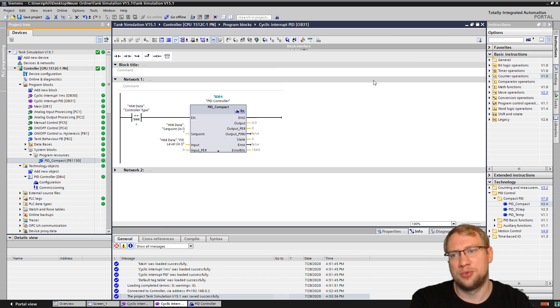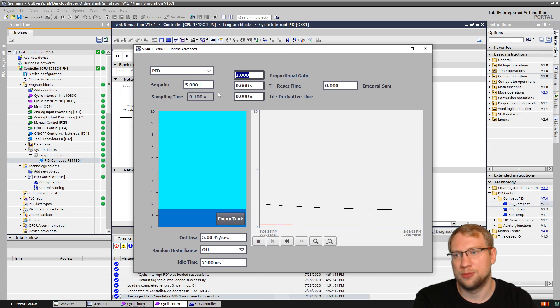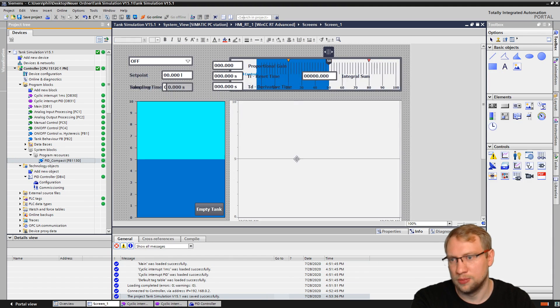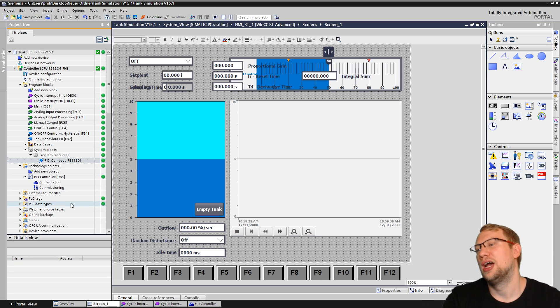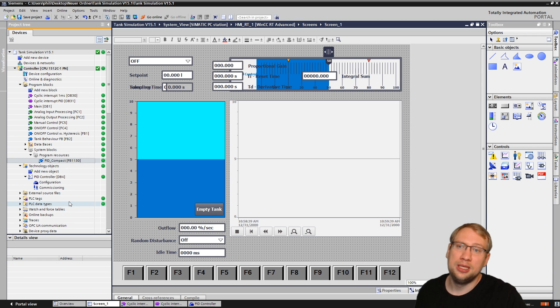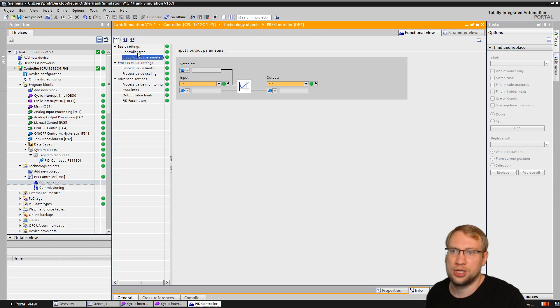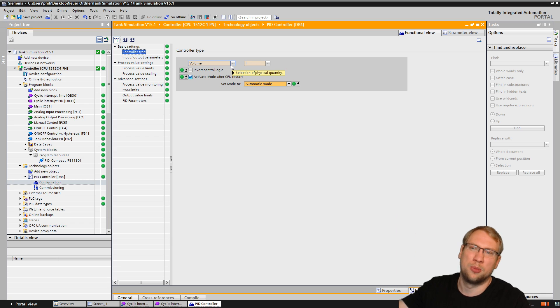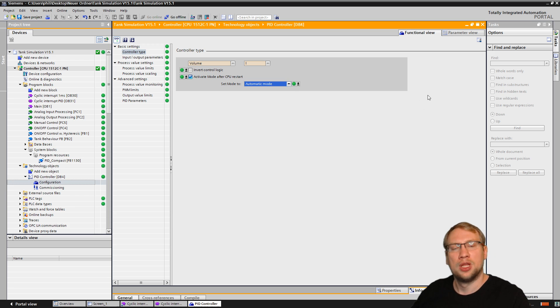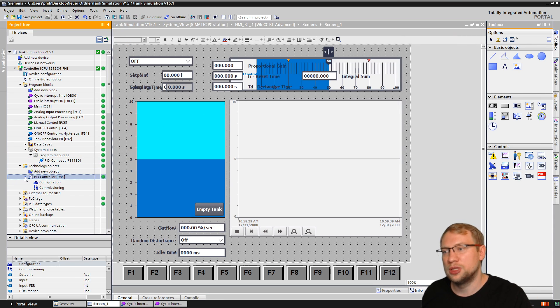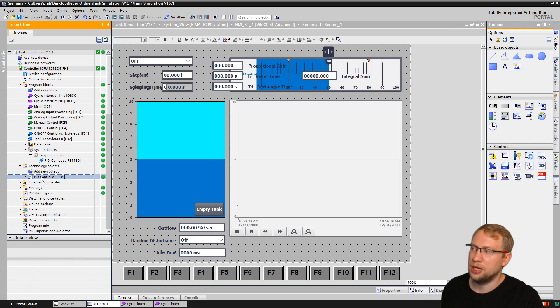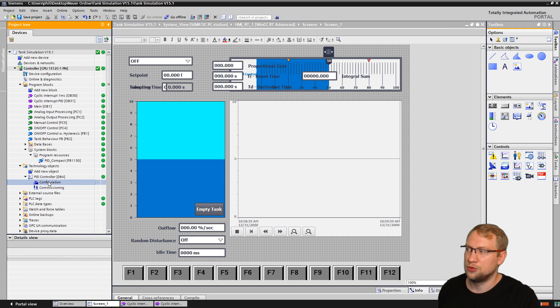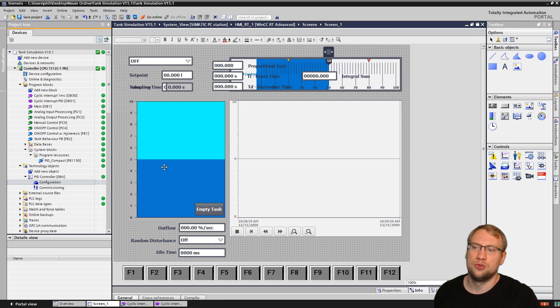The second way that I prefer is the following. So we've got our HMI here. I'll just make a box down here real quick. And on this HMI, I want the P, I, or D factor or anything else that has to do with the PID Compact block. We can also change, for example, the type. What do we want to measure? Volume? Which mode do we want to have? Right now it's automatic mode, which is mode three. We can change all that in the runtime. For this, you will have to go, after adding the PID Compact block to your program, go to technology objects, and there we have the PID controller. You can do the configuration, that's the one you just saw. But what you can also do is the following: on the PID controller itself, you can right mouse click, and there is the so-called DB editor, the data block editor.